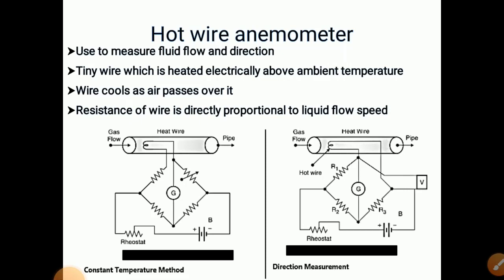On the right hand side, a similar diagram is shown with the same bridge circuit, and one extra terminal is taken out for measurement of direction. Depending upon change in direction, the voltage produced is either positive or negative so that we get direction of flow. Like this, hot wire anemometer is useful for measurement of fluid flow and direction.